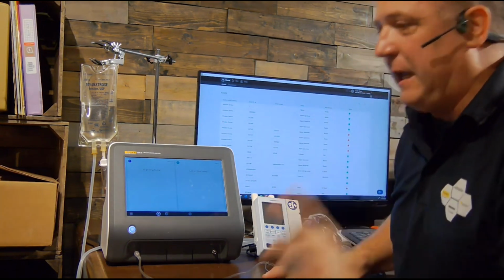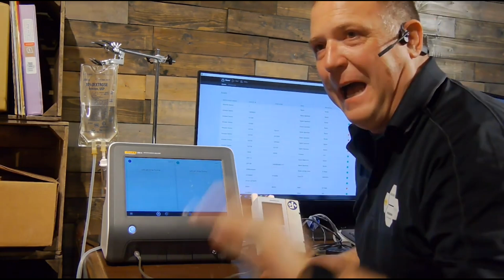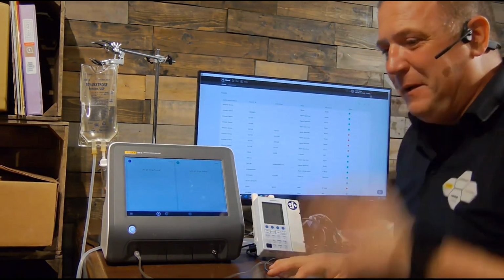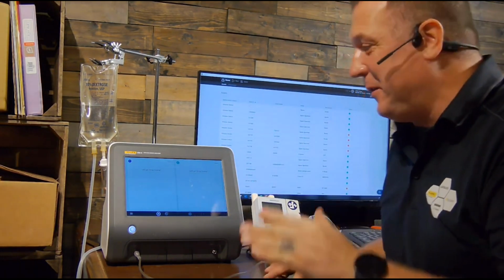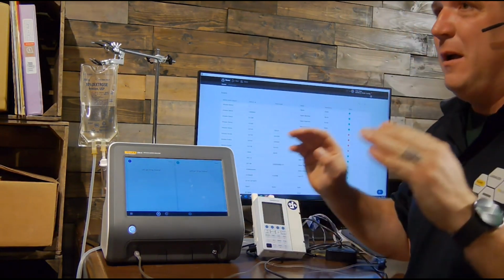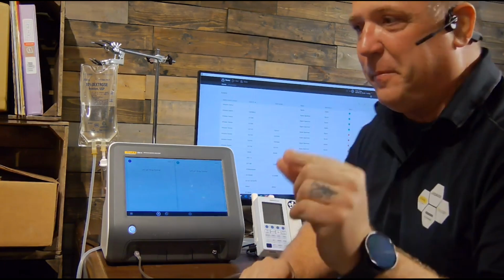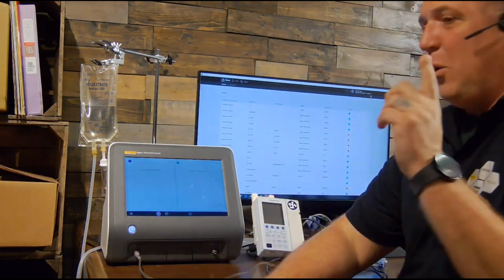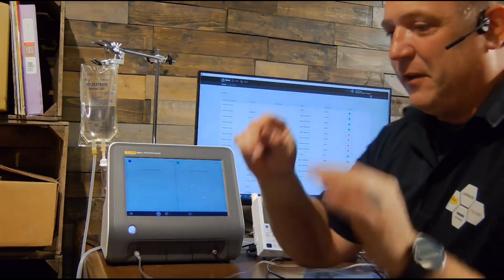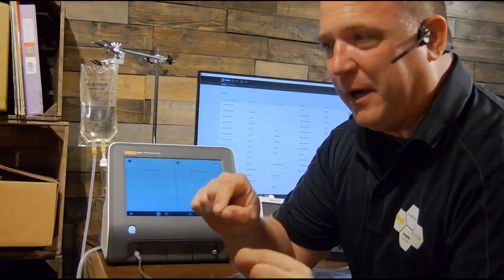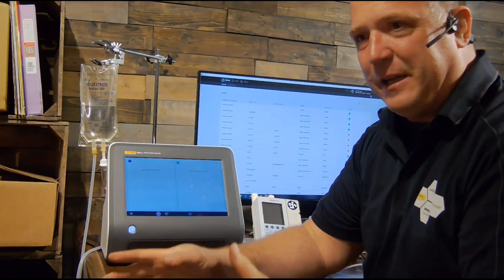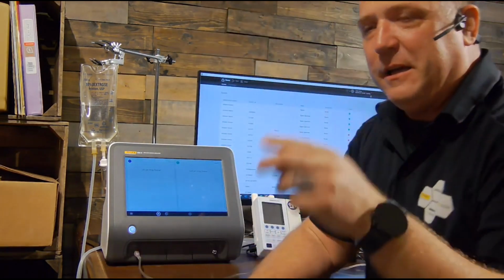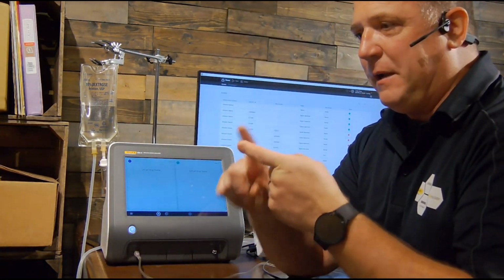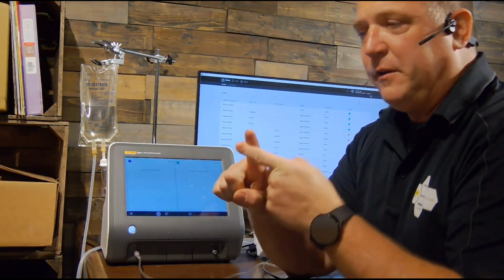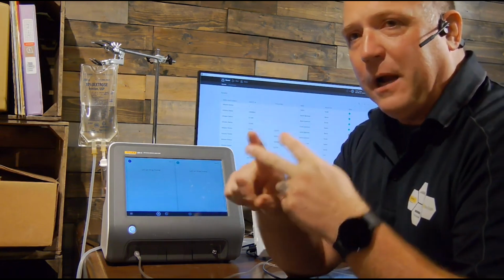Wait. One more thing. For my Alaris users, a little hack. I've been doing a lot of Alaris testing with my customers, and I found this to be so helpful. You have to use your imagination here just a little bit. For all my Alaris techs, what I've been doing is I use 2 channels because I still have to use that Alaris software, right? So I have the Alaris software on my PC, and I'm running it, but you need to have 2 sets. Alaris recommends that you have a calibrated flow tubing set and a calibrated pressure tubing set.